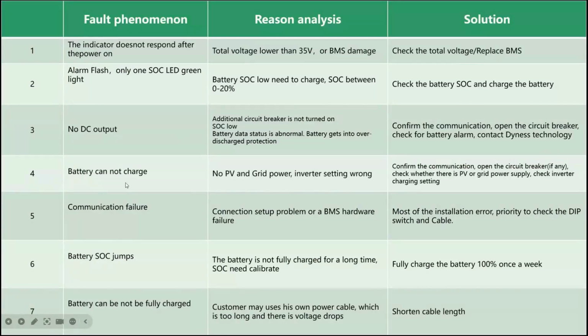And another: the battery cannot charge. I have seen many customer feedbacks that the battery cannot charge, and after I did detection and made a video call with them, I found that actually it's not a battery problem, because when the battery needs to charge, it needs power supply from PV or from grid. So first we need to confirm whether the circuit breaker is turned on, and then confirm whether there is PV or grid power. And then we can check whether the inverter setting is correct or wrong. Maybe now it says 4 o'clock p.m. and this site's battery is set to charge with no discharge in this time schedule. So we need to confirm the inverter settings.